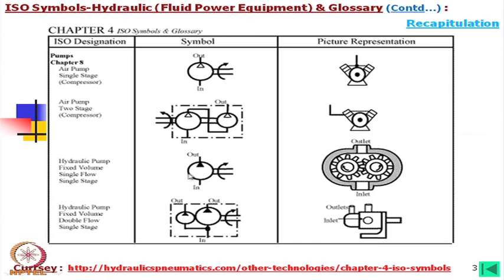This is a rotary hydraulic pump with fixed displacement. This is a double pump on a single shaft — both pumps are operated, one is of low flow and one is of high flow. Such pumps are used for energy saving: at high flow and low pressure both pumps work, and at relatively low flow and high pressure, only one pump operates.